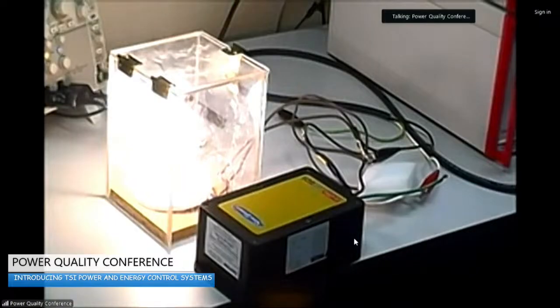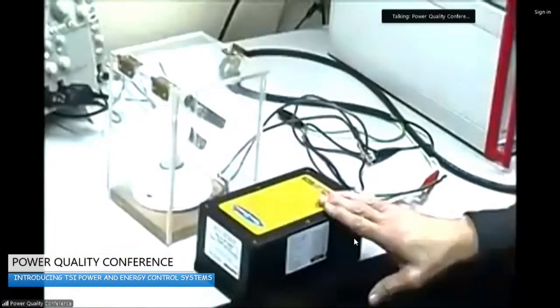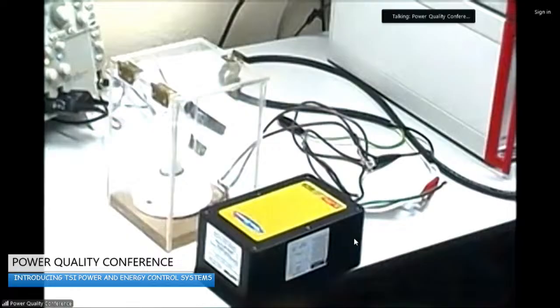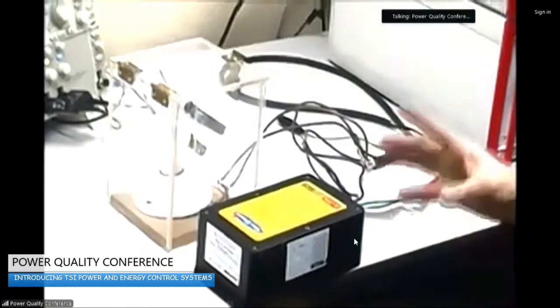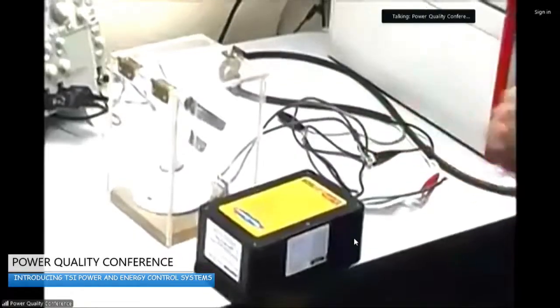Release the surge. No impact on the bulb whatsoever. Let's do this test one more time, and in fact we could continue to do it multiple times, but just so you can see it happen, let's charge it again. Release the surge. And again, just a flicker. Now you can see the benefit of having the Sinetamer suppressor with its lower residual let-through voltage rating to absolutely provide complete protection for electrical and electronic equipment.